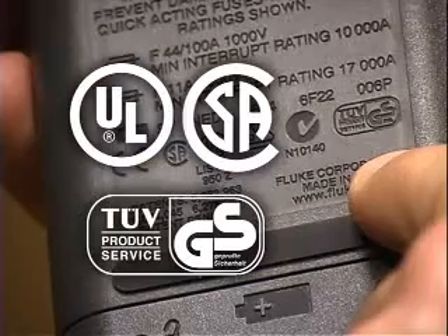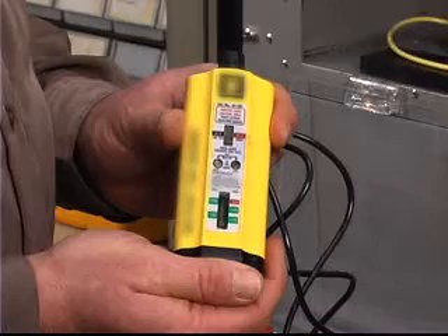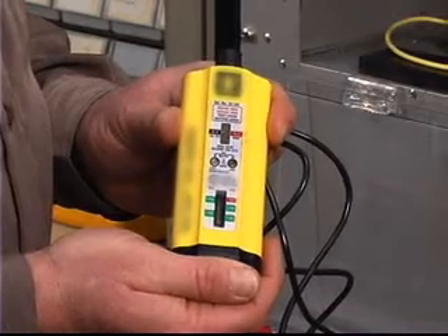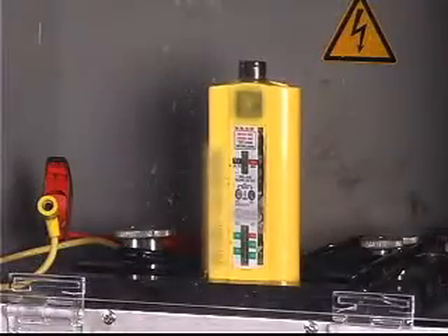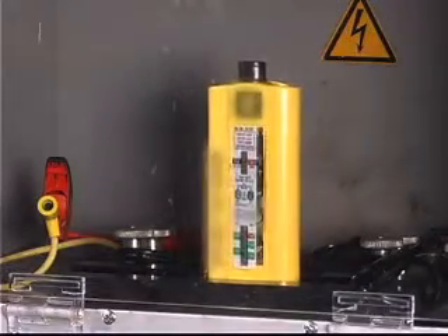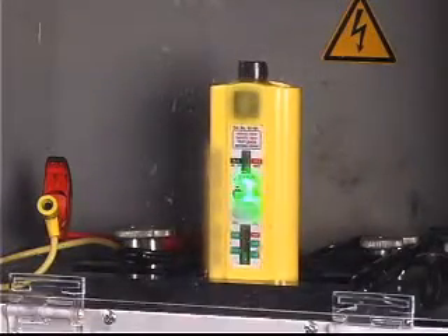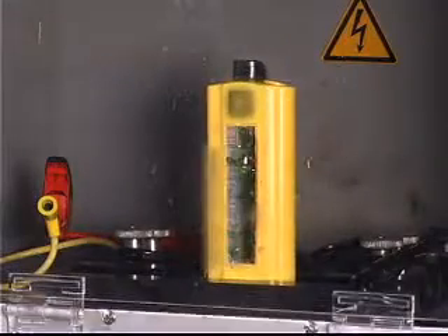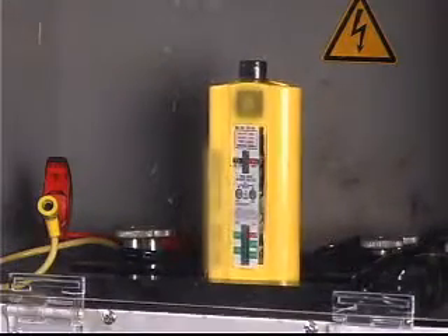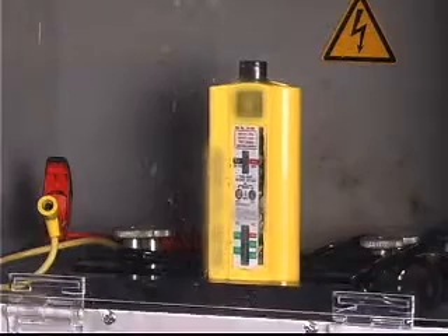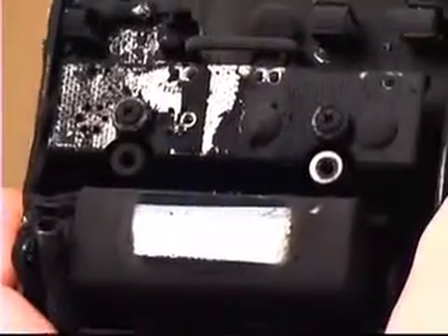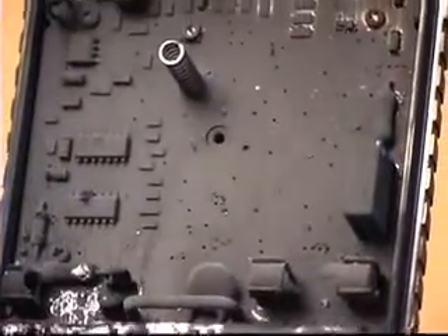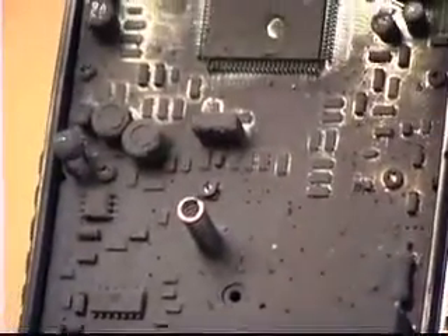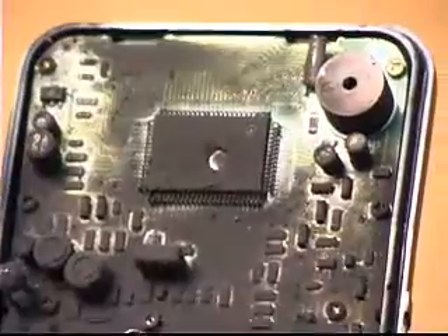applicable standard. Here's what can happen when a meter marked Cat 2 is used in a Cat 3 environment. In a real Cat 3 or Cat 4 environment, the arc would have been fueled by thousands of amps. The resulting arc flash could cause serious damage to people and equipment. In addition to the right kind of transient protection, a meter should be able to withstand accidental overloads associated with the various functions of the meter.